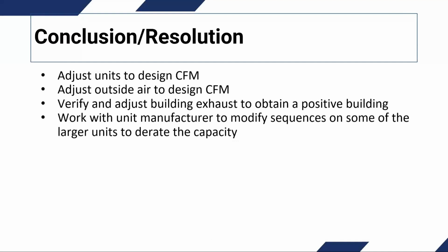We have a really good relationship with this particular manufacturer. So we were able to get, even though this job was in Oklahoma, we had some Dallas reps for the unit manufacturer to come up and assist us with modifying the sequences. Some of the units we ended up derating. So we may not have needed the capacity that was there. So with the manufacturer's assistance, we changed the sequences to where on some of them, instead of starting the small compressor first, they started the larger compressor. It just depended on the unit, what we needed to do to make sure that unit was reaching dew point when it was running the longest we could get it to run. Because the key to removing the moisture is to reach that dew point and to keep it at dew point as long as possible.